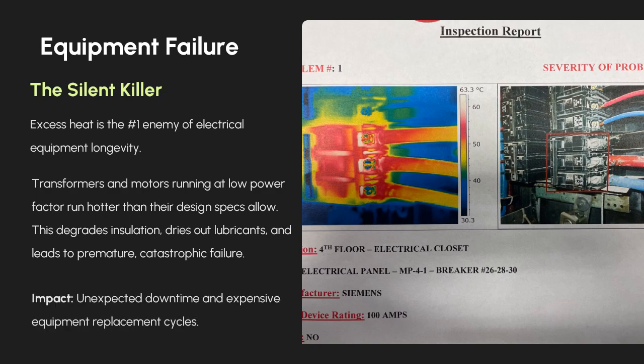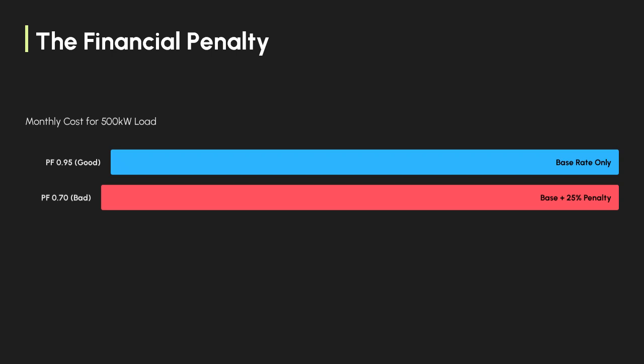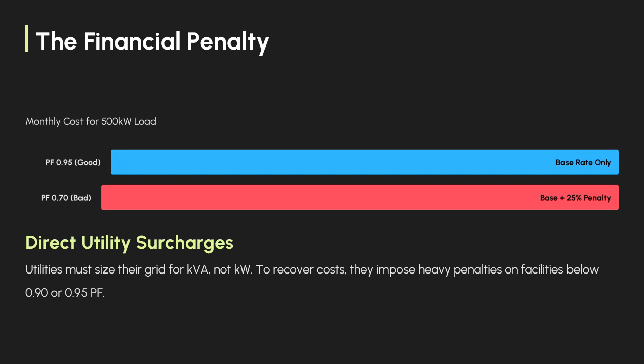The financial penalty. In addition to internal losses, a low power factor results in direct financial punishment from the utility company. Utilities must size their grid infrastructure based on apparent power, or kVA. To recoup the cost of generating and transmitting non-working reactive current, they impose significant surcharges on customers who operate below a specified power factor threshold, often 0.90 or 0.95. As our simple chart illustrates, a poor power factor can easily add 25% or more to your monthly bill. Correction equipment offers an extremely fast return on investment, often less than 2 years, simply through penalty avoidance.